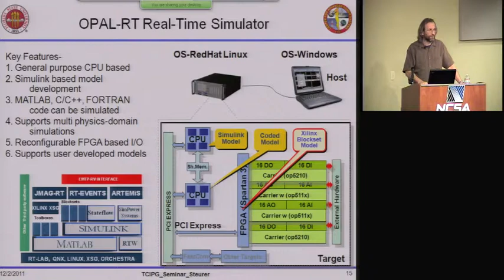In controller-in-the-loop setups, as I said, there's no power interface—it's mostly digital-to-analog connections, wires coming out of the simulator sending an analog equivalent of voltage and current to a controller. The controller, typically for power electronics, sends firing pulses for power electronic switches, and those switches are then simulated in their turn-on and turn-off events in the real-time simulator.